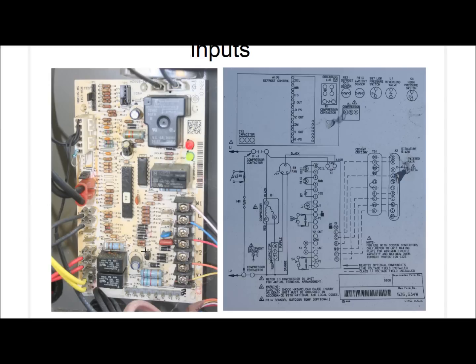So let's start out with the control wiring connections. On this defrost control board, there's a nice terminal block. Some defrost control boards will not have a terminal block, and these will be wire nutted into a little pigtail. The other thing to note is this is a general overview of how defrost control boards work. They're all a little bit different, but this is just a general overview to help you understand it. In later lessons, we'll get into some different control boards and how they operate differently, but this happens to be a Lennox, and this is pretty indicative of what you're going to see.